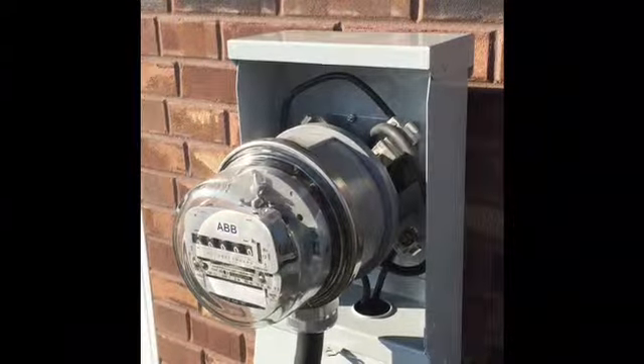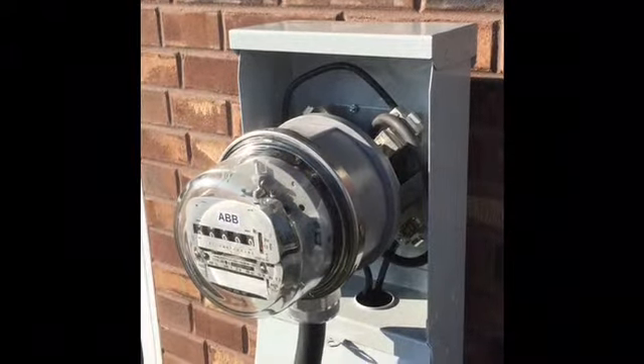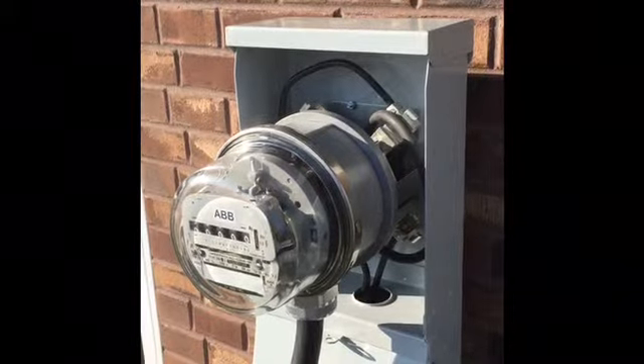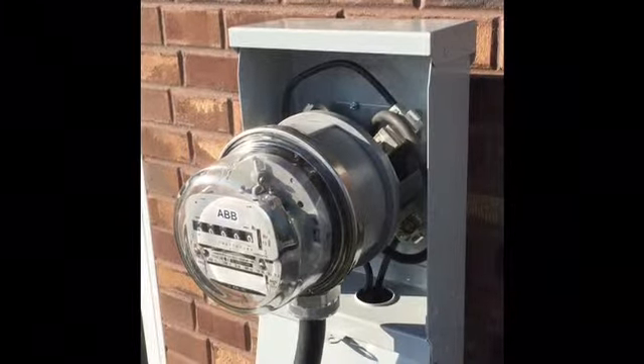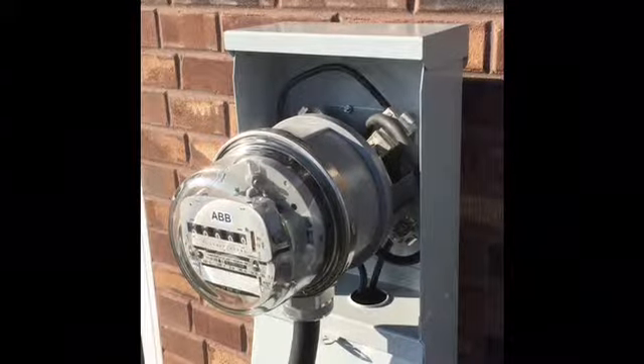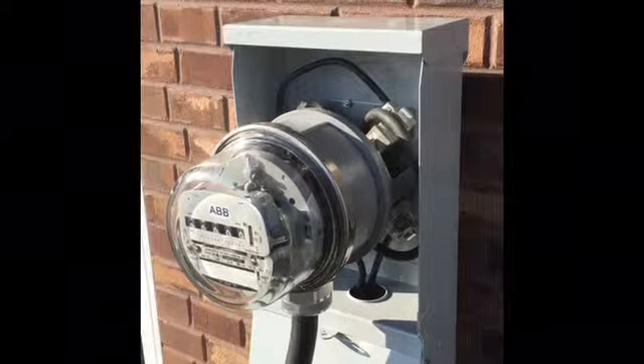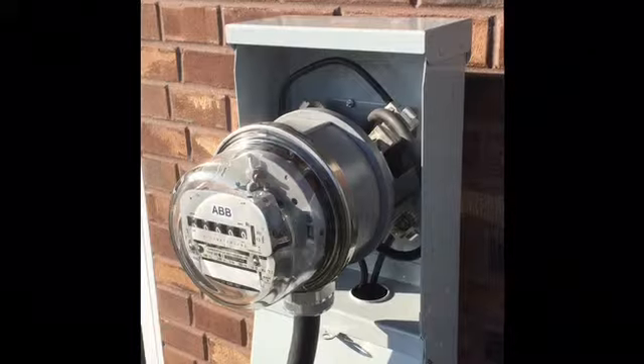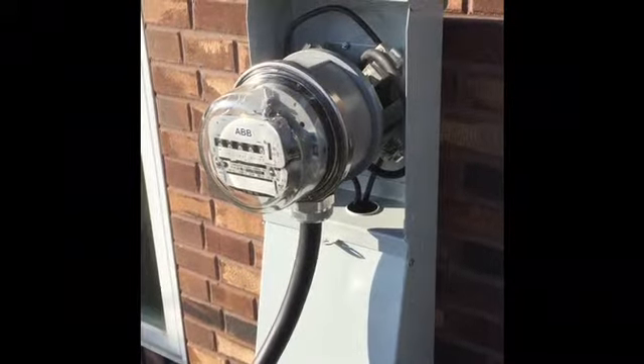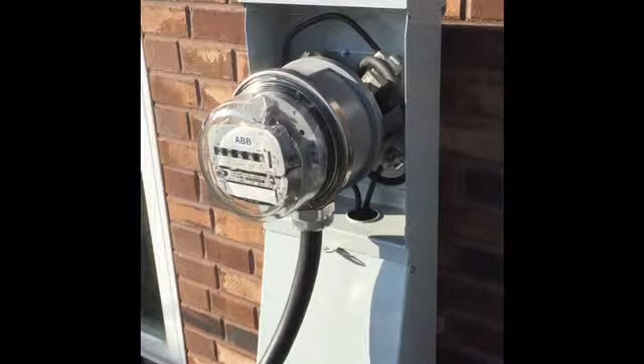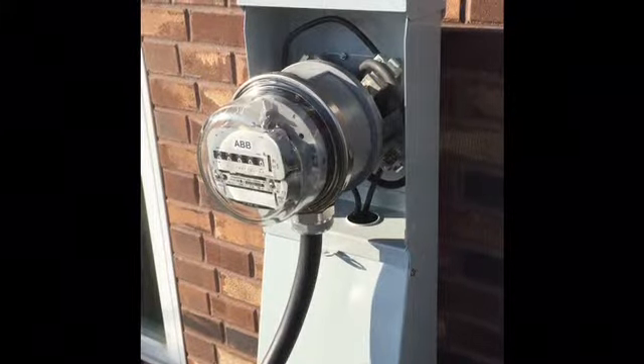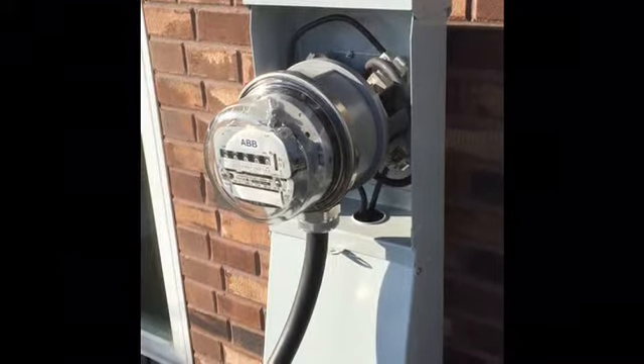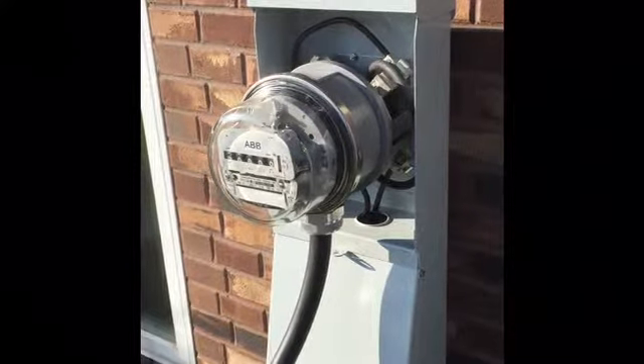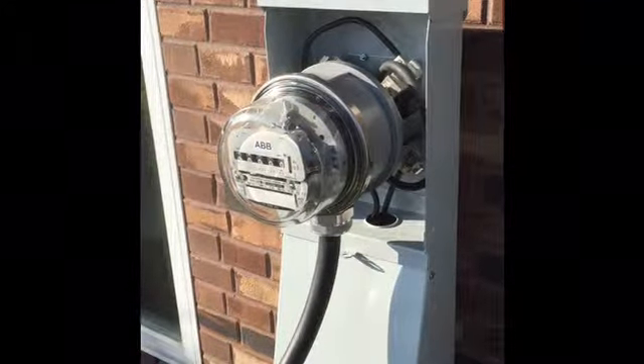So in that case, if the customer looks like they're exceeding that, have them lessen their load, and they have to make sure that they maintain their load at that lower level, so we don't exceed the rating of the system. And yeah, then once you've established that the current levels and the voltage are at acceptable levels, the first thing to do is go in and turn the customer's breaker off again, and then we go and turn the breaker off at the can.